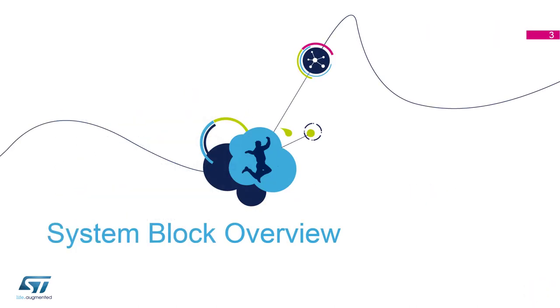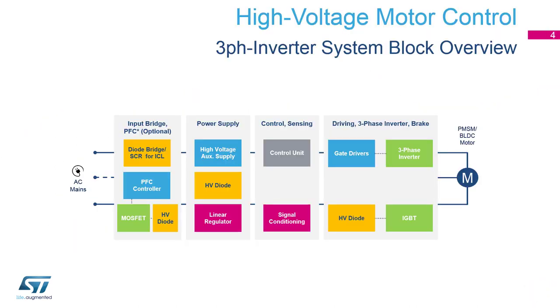System block overview. On the left side of this system block overview we see the AC mains input. It can be single-phase or three-phase. The AC mains voltage needs to be rectified into DC voltage using a diode bridge. In case of in-rush current limitation, an SCR or TRIAC could be found.